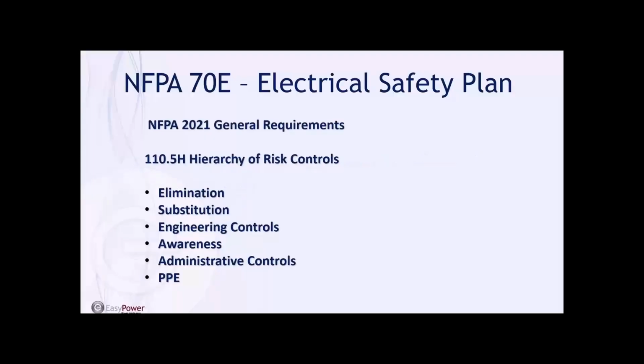The next article is 110.5H, which now brings into the 70E standard a kind of standardized safety protocol for when you're dealing with risk—what's that hierarchy of how we look to control or work with that risk, stepping down all the way from eliminated to the last resort being personal protective equipment. We know within our industry that we've pretty much relied on that last tier of PPE and some of these other elements like eliminate or administrative controls.